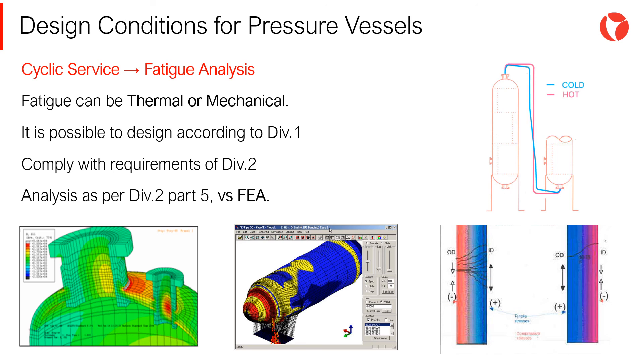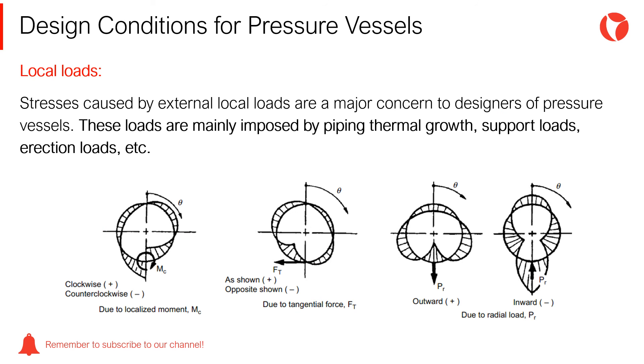Some vessels are subjected to periodic repetitions of mechanical and thermal loads during their service life. When a vessel is subjected to repeated loadings that could cause failure by progressive fracture, the vessel is considered to be in cyclic service. Stresses caused by external local loads — mainly imposed by piping thermal growth, support loads, and erection loads — are a major concern to designers. These stresses must be combined with stresses produced by sustained or permanent loads.